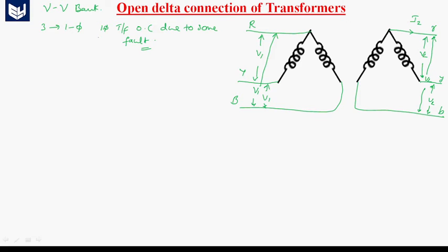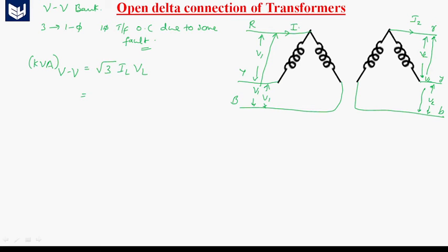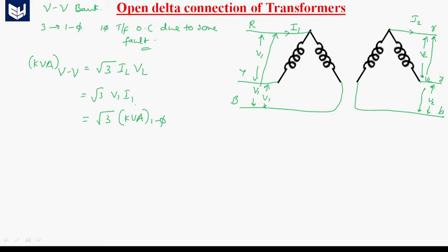The KVA rating of the open delta connection is root 3 into VL into IL. Here VL equals V1 and IL equals I1, so the KVA of open delta equals root 3 into V1 into I1. Since V1·I1 is the KVA rating of a single phase transformer, the KVA of the open delta connection equals root 3 times the KVA of a single phase transformer.